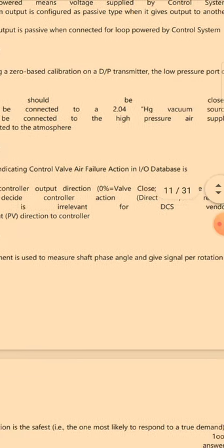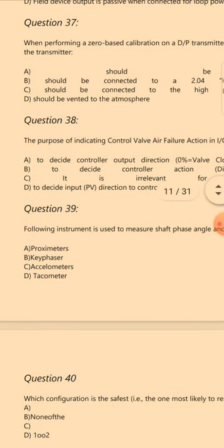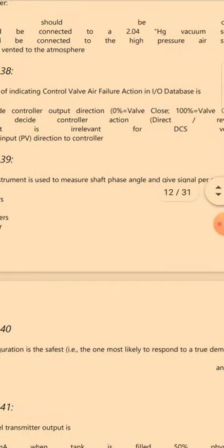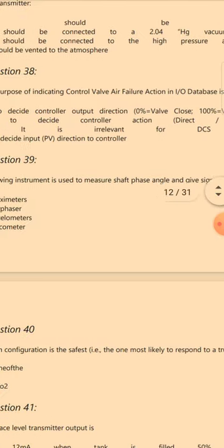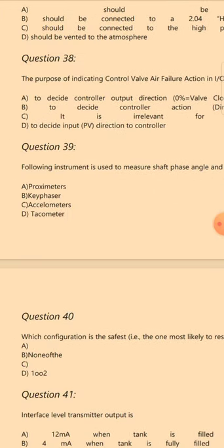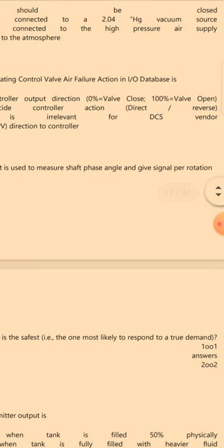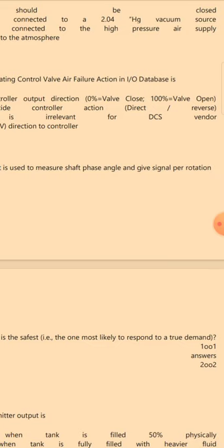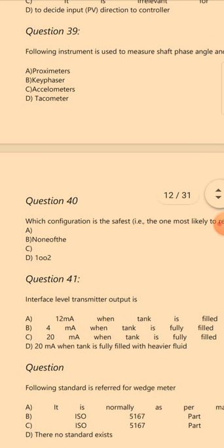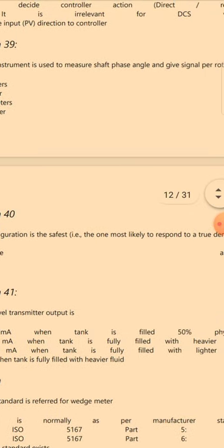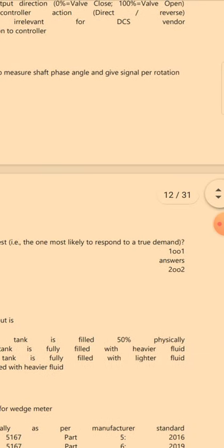Question 36: Select the false statement for analog type input/output — the answer is A: When a field device has active output, it means the control system should not give voltage for loop powering. Question 37: When performing a zero-based calibration on a D/P transmitter, the low pressure port — the answer is B: Should be connected to a 2.04 inch of mercury vacuum source.